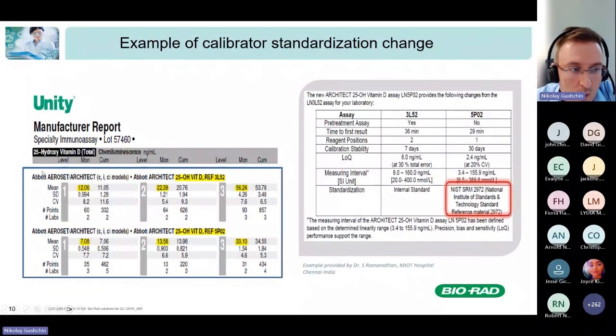One peer group on the top and one on the bottom. The only difference between the 2 peer groups is that they were using a different calibrator with different reference numbers. So you see this reference mentioned, 3L52, and for the second peer group, another reference. And just have a look at how the numbers are different. For example, for level 1, in one group we have 12, in the second group 7. For level 2, 22 and 13. And level 3, 56 and 33 in the second one.